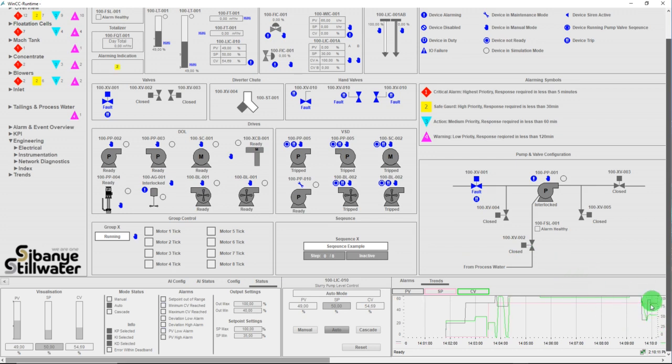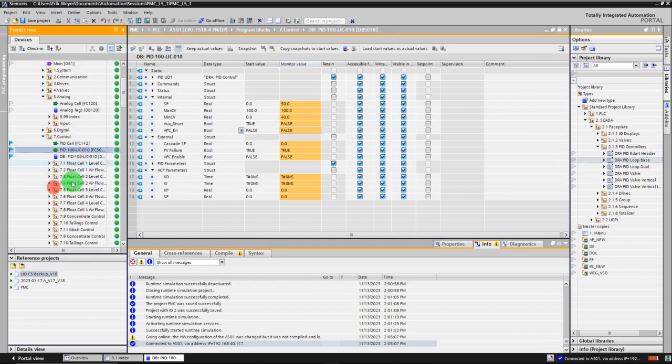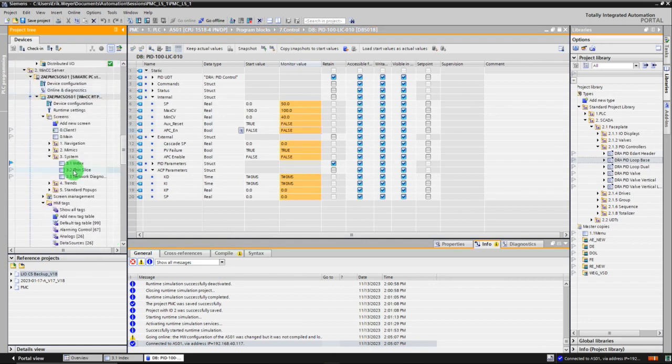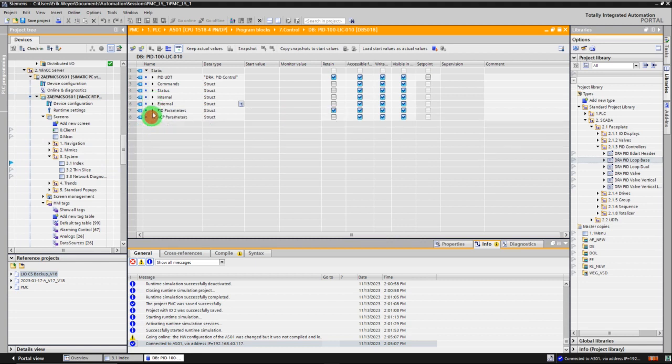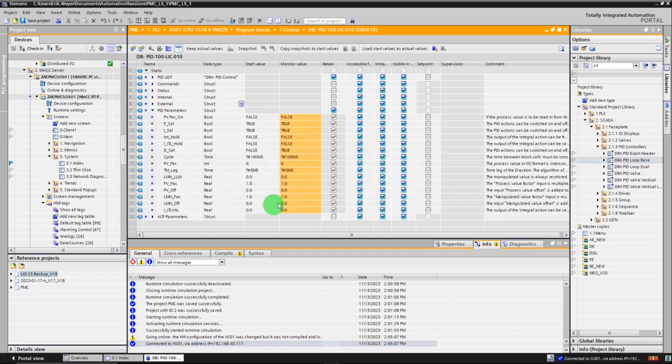As you can see here from the trend, we've played with it a little bit. If it's a highly advanced loop that you want to tune, and from the scaler it might be a little bit difficult and you want additional parameters to play with, you can come into the PID parameters in the DB, and I've got functions like, for example, my cycle time.